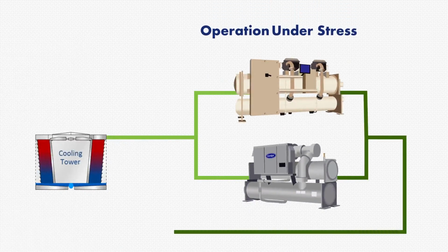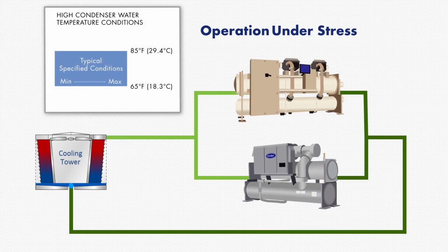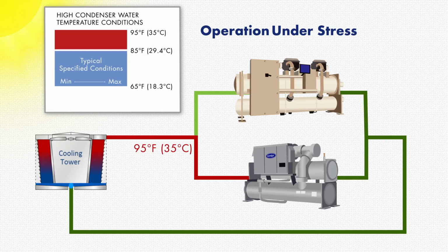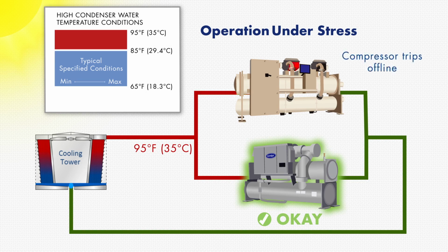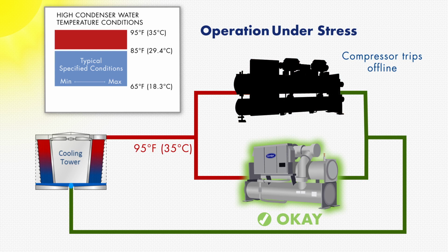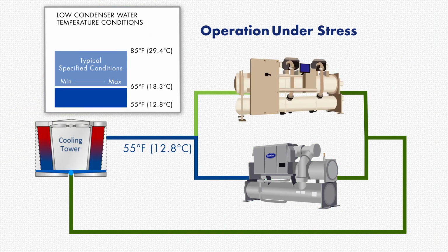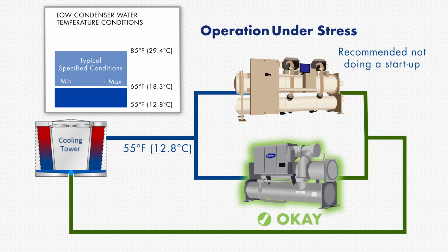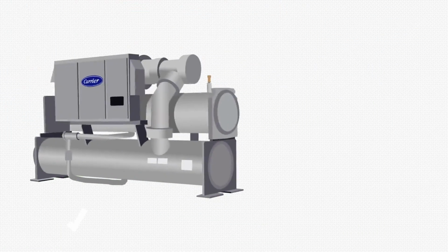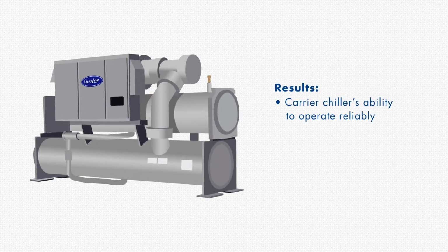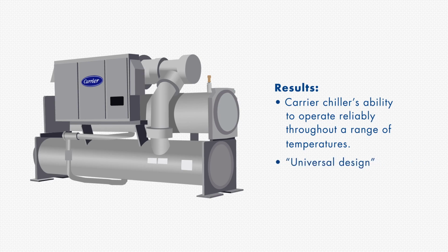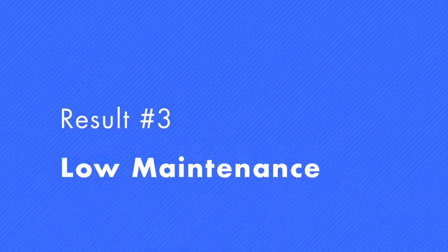When put to a stress test, the Carrier chiller showed greater operating versatility, providing an increase in system reliability. At entering condenser water temperatures of 95 degrees Fahrenheit, the Carrier chiller operated normally without any signs of distress. The mag-bearing, however, had a compressor trip offline. When conditions demanded low condenser water temperatures, the Carrier chiller was able to satisfy building cooling, while the MBC manufacturer recommended not doing a startup. The results illustrate the Carrier chiller's ability to operate reliably throughout a range of temperatures well above or below design conditions, earning the VSS compressor the distinction as a universal design.